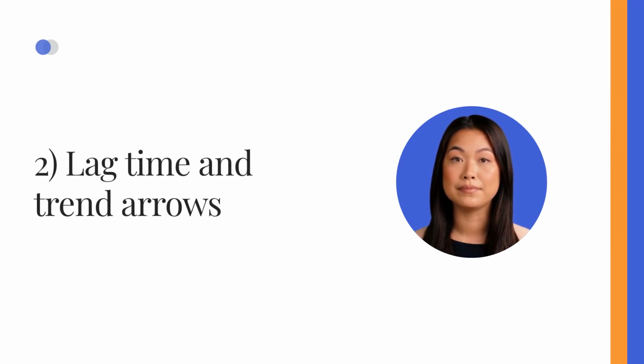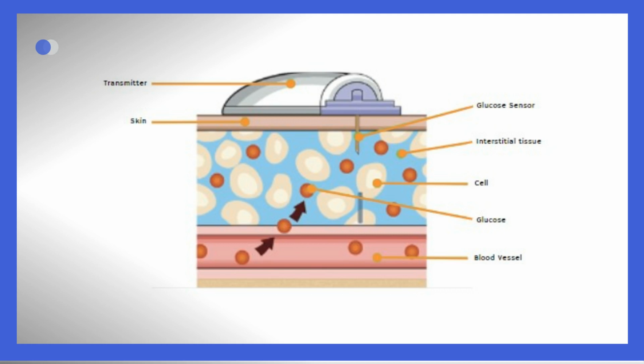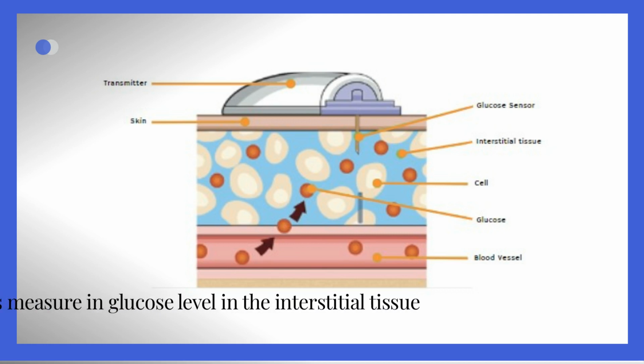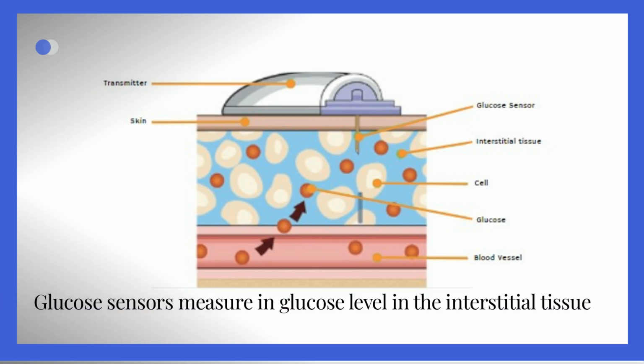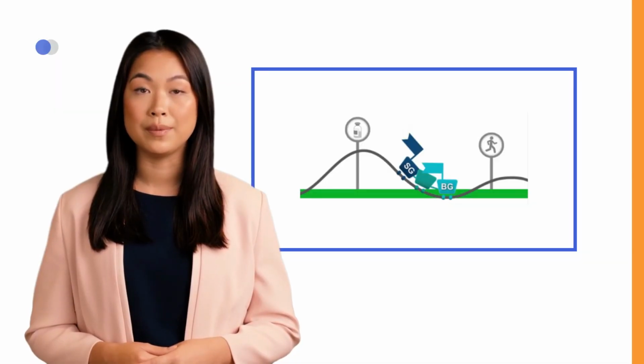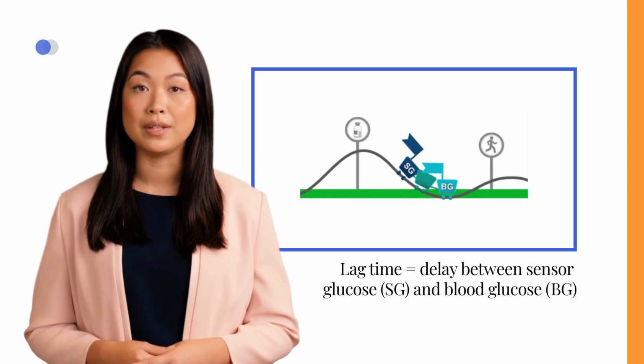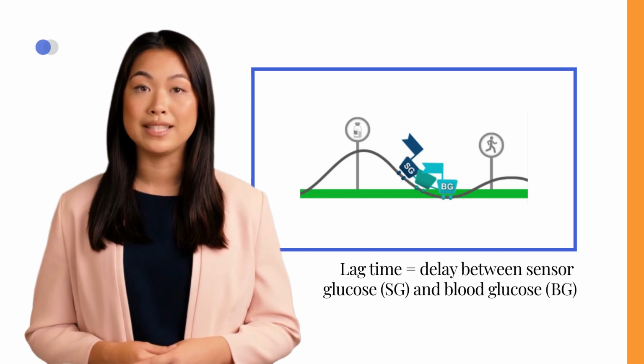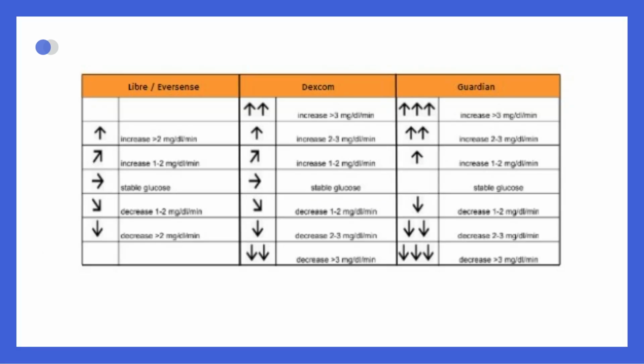2. Lag time and trend arrows. Glucose sensors measure glucose levels in the interstitial fluid within the fatty tissue below the skin. There is usually a delay known as lag time between changes in blood glucose and the sensor's detection of these changes. In general, the lag time ranges from 5 to 10 minutes but can extend to 15 to 20 minutes during times of rapid glucose change. This lag time plays a critical role in how we interpret trend arrows.